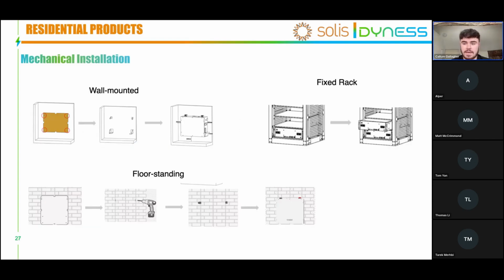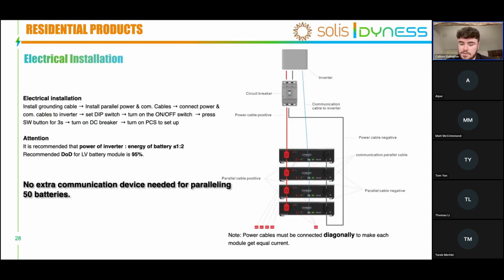This is for wall mounting here. It's exactly the same as the PowerBox G2. Screws into the back, screw the bracket onto the wall and then just slot that in there. And if you're floor mounting it, just make sure that's fixed in place. And that's just a little guide there. Positive to positive to positive, negative to negative to negative, and then feed back round to the circuit breaker and then into the inverter.